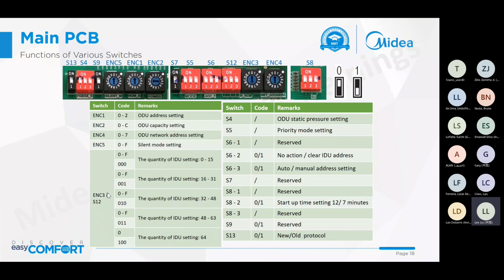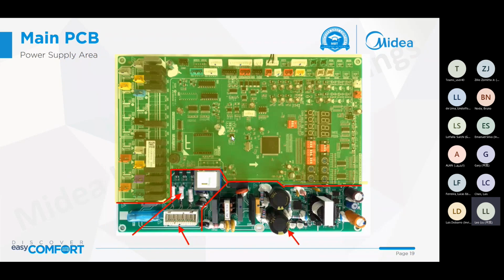And the quantity of the online indoor units is set by combining the DIP switches ENC3 and S12. There are also the outdoor static pressure setting and the priority mode setting, a lot of DIP switches for different function settings here. Okay, on the main PCB, we can see the down arrow; this is the power supply area.